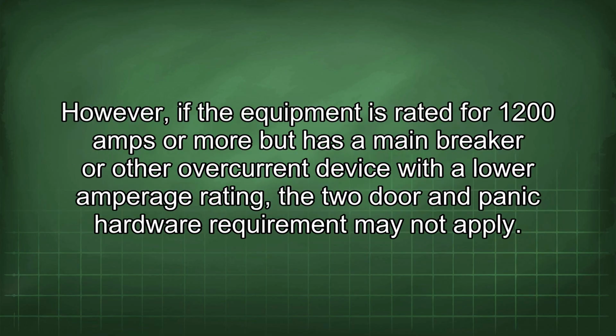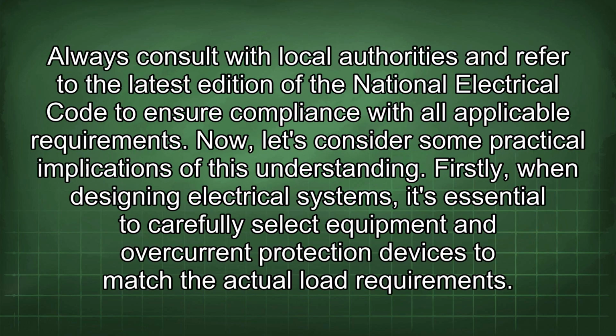However, if the equipment is rated for 1200 amps or more but has a main breaker or other overcurrent device with a lower amperage rating, the two-door and panic hardware requirement may not apply. Always consult with local authorities and refer to the latest edition of the National Electrical Code to ensure compliance with all applicable requirements. Now let's consider some practical implications of this understanding.